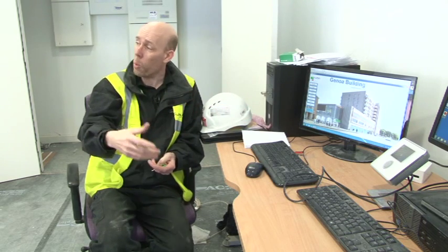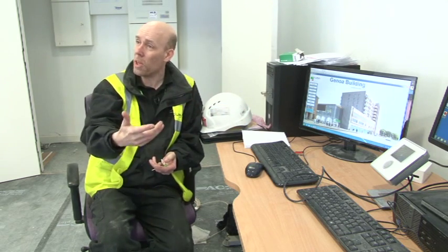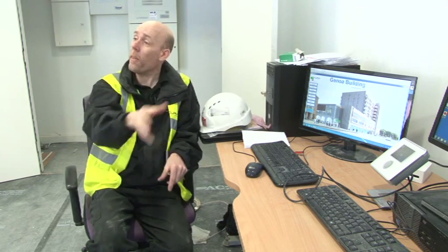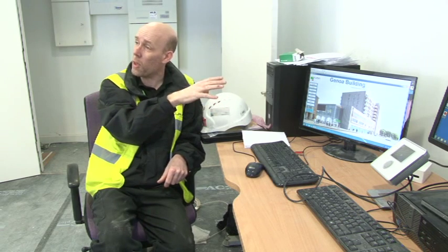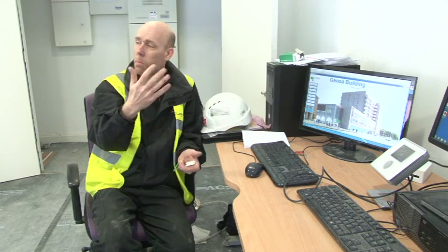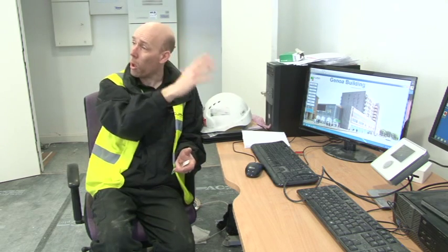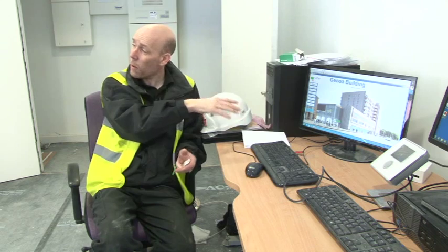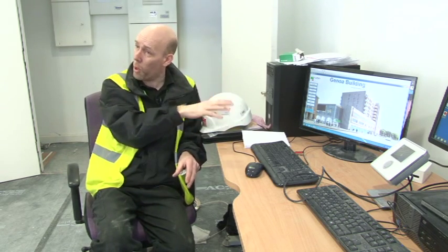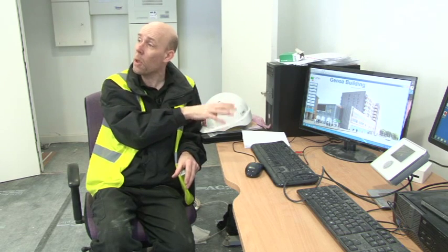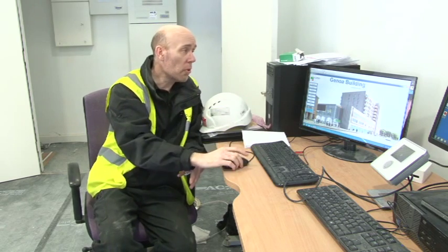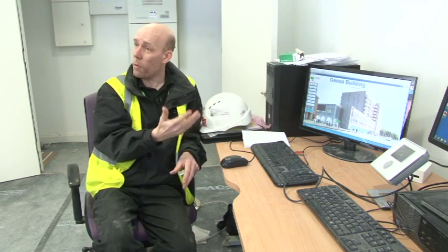Other alarms will require a manual intervention to say, I've fixed the fault, I've done this, this and this, and then it records that information as the log of the fault. So things like if a pump fails, it will latch the alarm on here, and until somebody types in an answer and the fact that it's been fixed, the alarm will permanently appear on this PC until such time as it's gone.